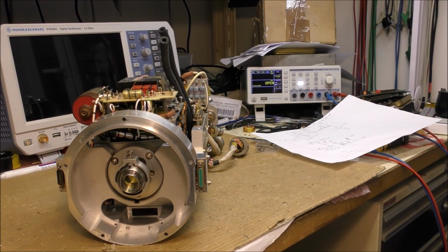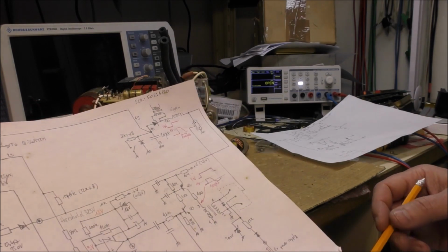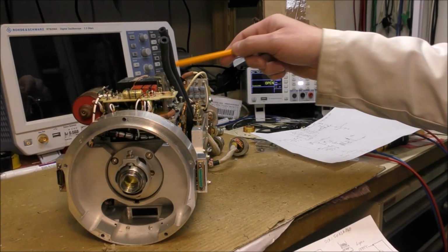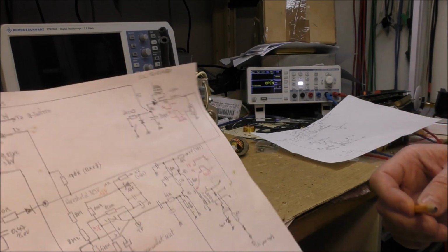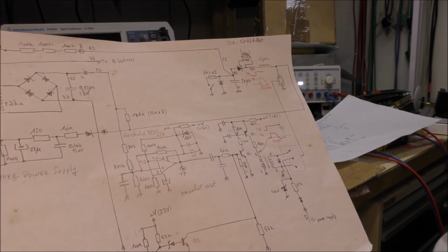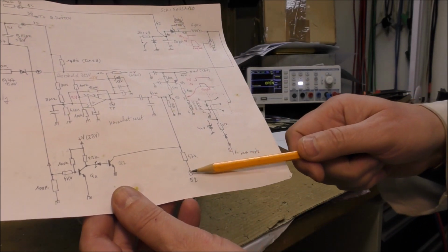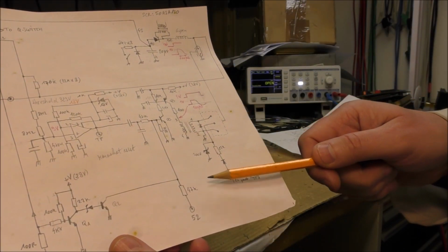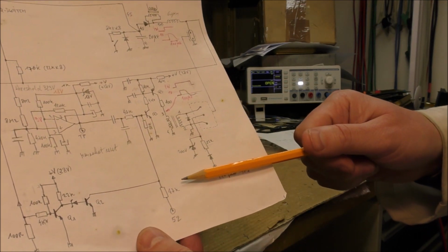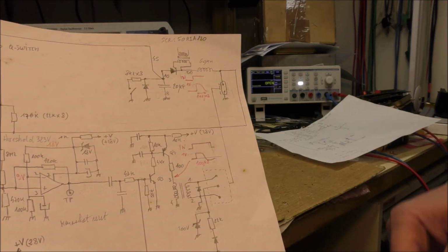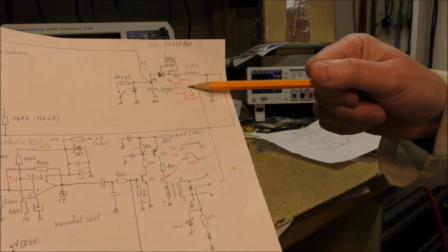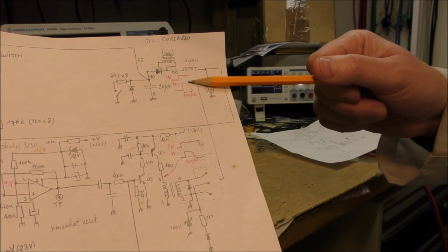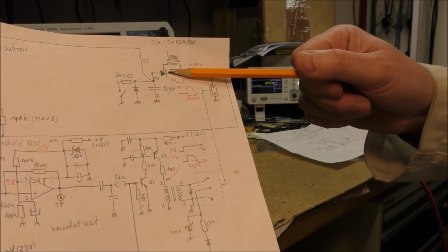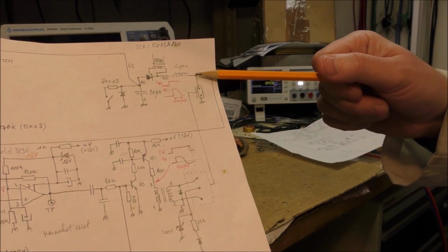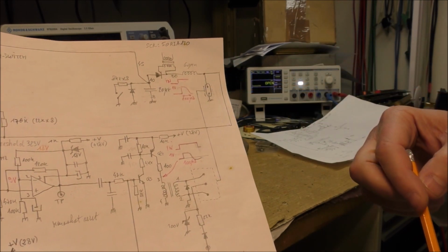First of all, I have already performed some tests on that device. So I have applied a voltage of 28 volts to that board here. So this permits the control of the lamp and the Q switch. The input is here. I have applied a pulse of 10 volts approximately, and the duration of 1 millisecond or so. I have checked that there is effectively a pulse. The duration of the pulse is around 100 microseconds in order to activate this SCR. So this permits to connect the discharge lamp to the capacitor, which should be previously charged.